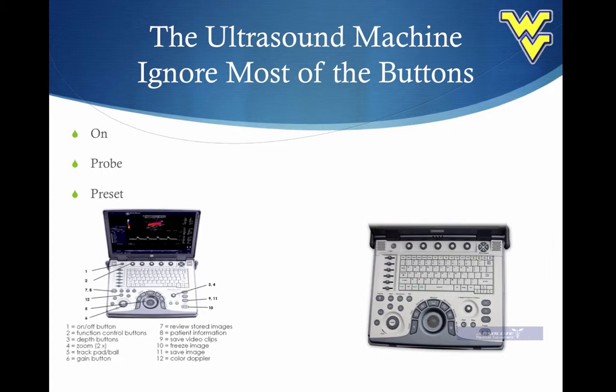Then there's a button that helps you select the probe. Now sometimes you may have to attach the probe manually, but most of the machines that we use have a selection where you can just select one of the probably 3 probes that are hooked up. And on these GE machines that we use in our lab a lot, it's down in here somewhere, you can select the right probe for the job. And then there's a preset button, and this machine is actually the same button, probe preset. And that's where you just, again, select your preset. Now you're going to ask me, how do you select these things? How do you work this?